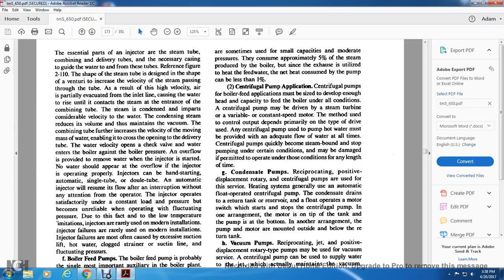Injectors can be hand-starting, automatic, single or double tube. An automatic injector will resume its flow after an interruption without any action from the operator. The injector operates satisfactorily under constant load and pressure, but becomes unreliable when operating with fluctuating pressure. Due to this fact, and to the low temperature limitation, injectors are rarely used on modern installations.